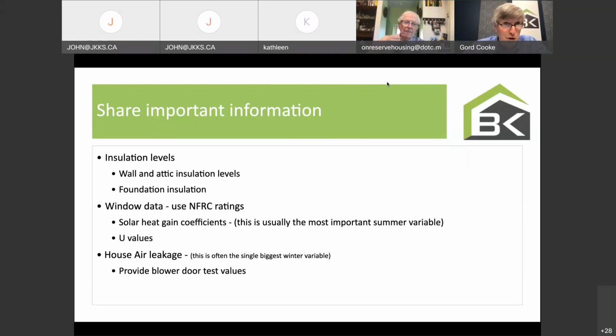Lauren and I do blower door testing. Some of you know what that is, which is you do air tightness testing on the building, and from that, you can predict the heat loss associated with air leakage. And here's what you need to know. I probably covered it in the last session. Nominally, about 30% of the size of your heating equipment is needed to replace the heat that's being wasted or lost through air leakage.